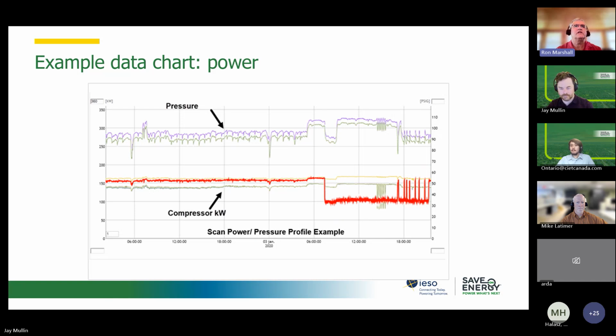So that's an indication for seasoned chart readers like me that the system is in drawdown. There's not enough capacity to feed the high flows. And then over to the right, we can see some sawtooth waveforms, right? That's an indication the compressor's loading and unloading. We can see one compressor, that big red fuzzy one, unloaded to a lower level, and it starts at the far right end of the chart. It's loading and unloading, so we can see from the power and from the pressure reading what's happening there, and we can understand what's happening.